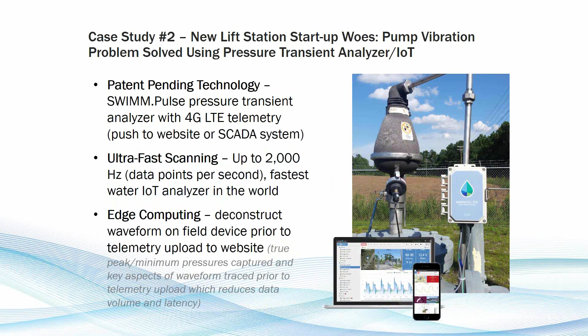So after watching the data for a couple of days, we started seeing a very obvious problem. The small pump there in the center graph in the middle, we've got the small pump operating at only about 3 psi, and we're seeing a lot of water hammer during shutdown. Transient pressure was peaking at 30 with a -7 low pressure, and the large pump had the same problem. And so it became more and more clear that we were kind of self-sabotaging ourselves and pulling air into the line by running this large pump. It wasn't really serving its purpose.